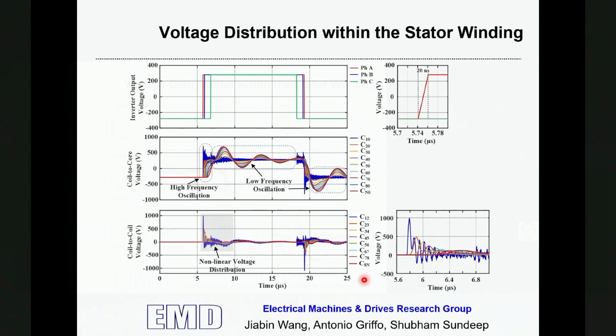And these 3 types of motor overvoltage do not drop equally on all the turns or all the coils. They normally drop on the first several turns of the winding. So the first several turns of the winding are most stressed. Okay, so that means the first several turns at the motor terminal and also the last several turns close to the motor neutral will be the most stressed turns. So their insulations will be stressed more than others.